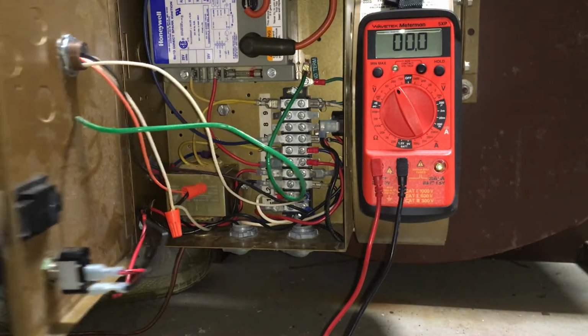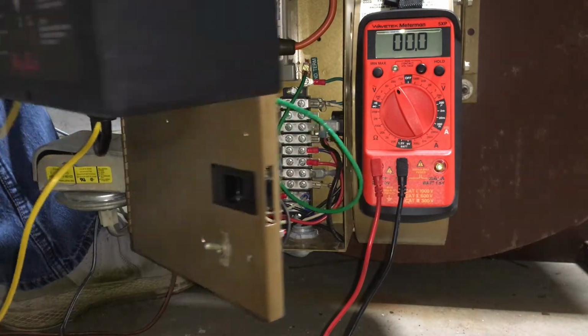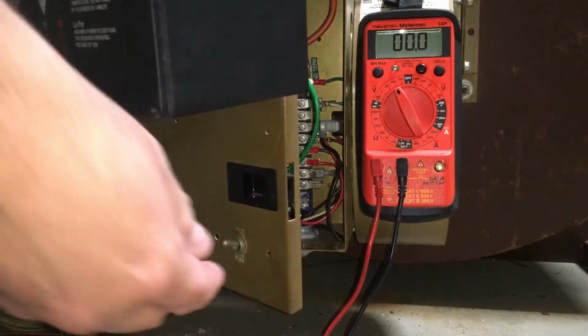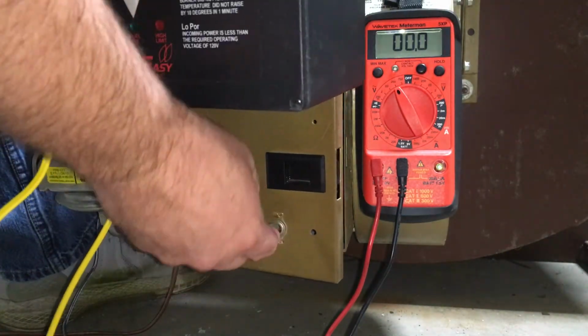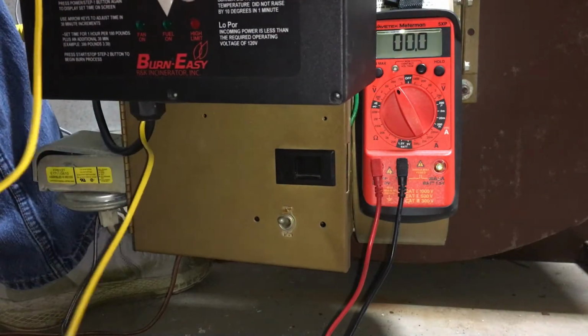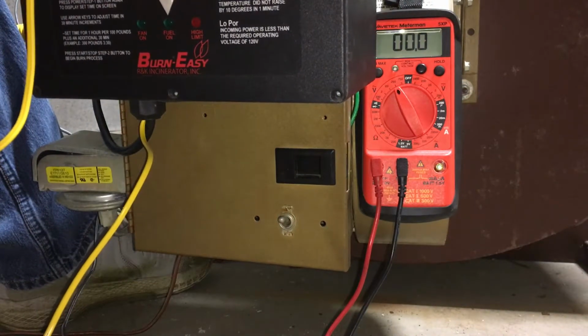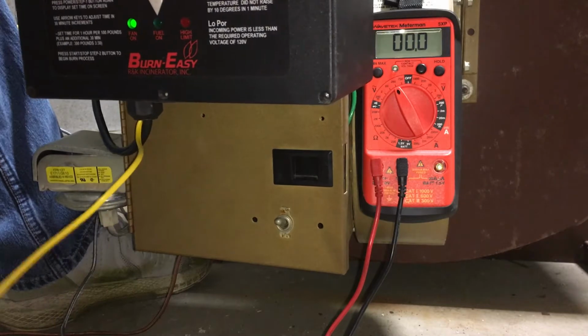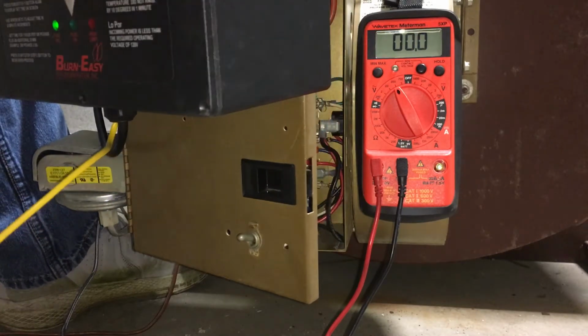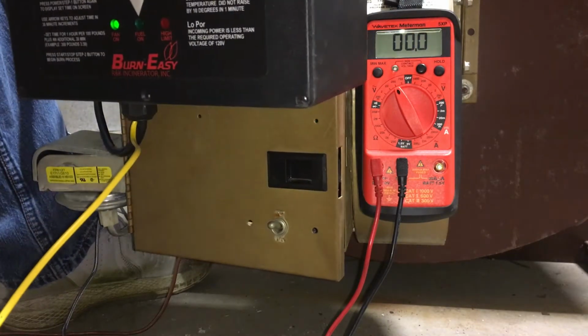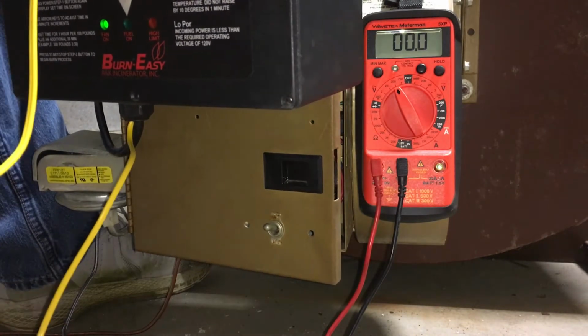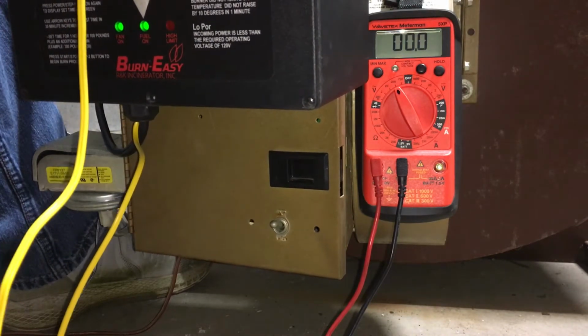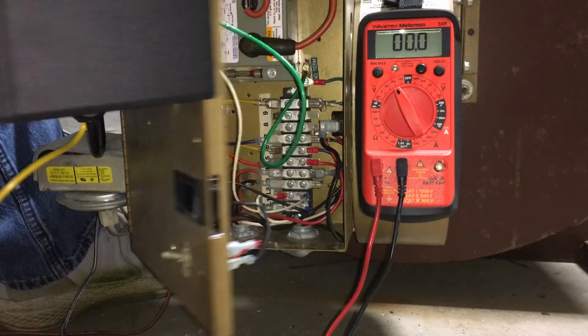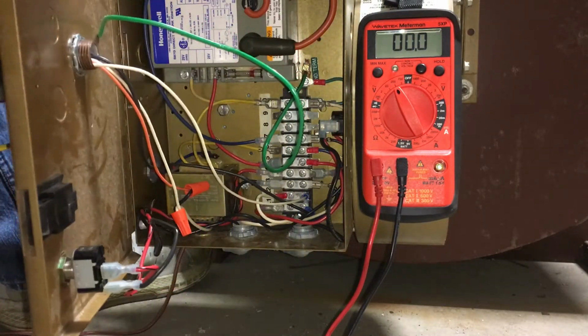So when you check all of these, everything must be in the state where the unit is supposed to operate. So you need to have your power switch on, and then you need to tell your control to go ahead and operate. As you can hear here, the motor is running, so we're in the operate mode. Right now the motor is running, but we can act as if the motor is not running, and we will go through and check all these.